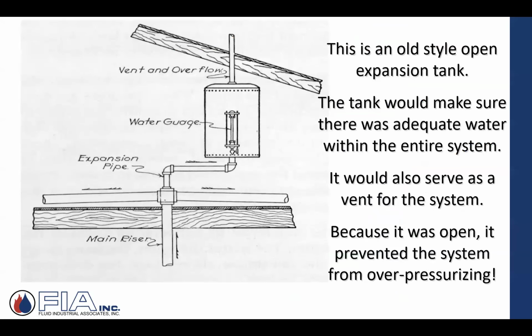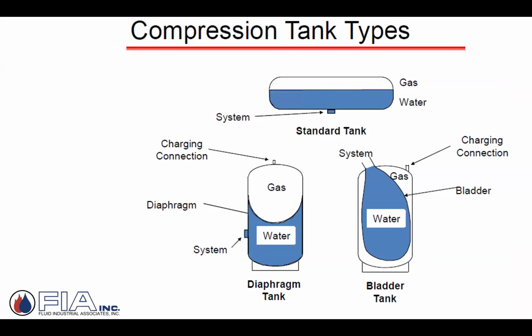Expansion tank, there was no compressing. It vented out of the system and the water just expanded into the tank. Once they sealed it and you weren't open to the atmosphere anymore, it was closed. Technically, you were compressing. And then as the water cooled, that spring would expand, that gas would expand. So it was compressing constantly, either squeezing or expanding.